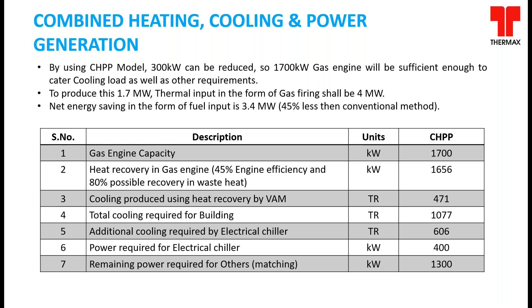So this absorption chiller running on the engine waste heat recovery can serve as the base load for meeting the cooling demand, whereas the electrical chiller can come into the picture when we are working on peak loads.